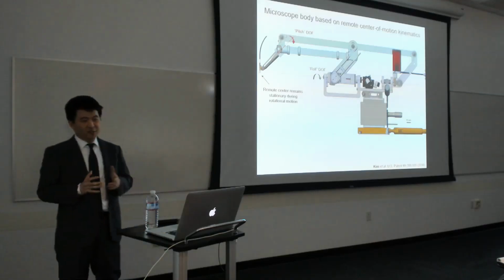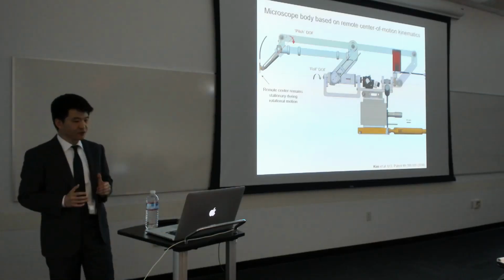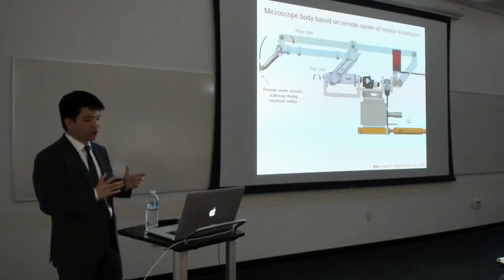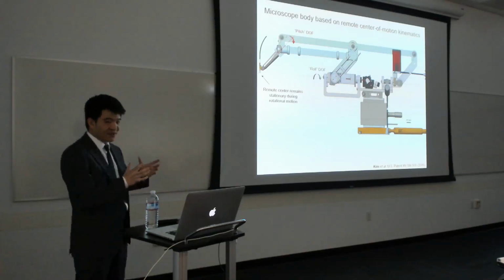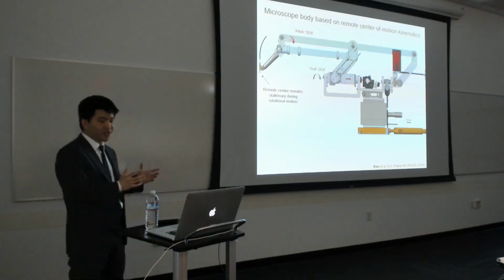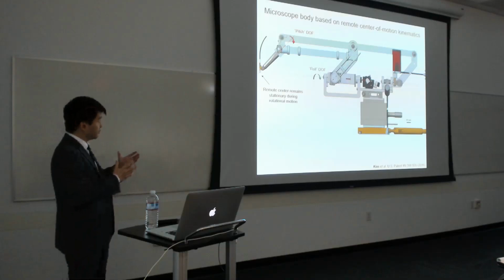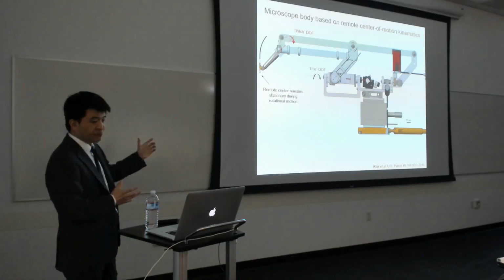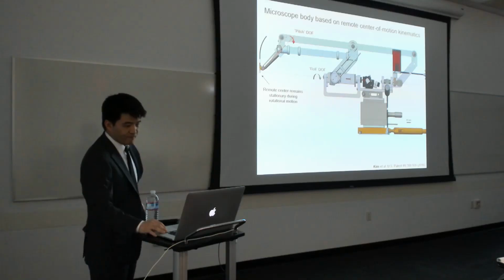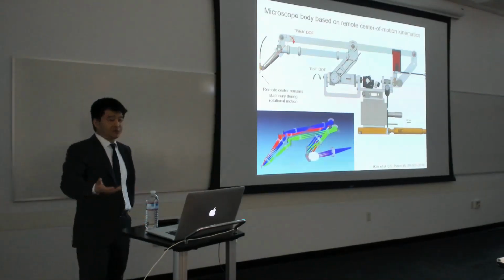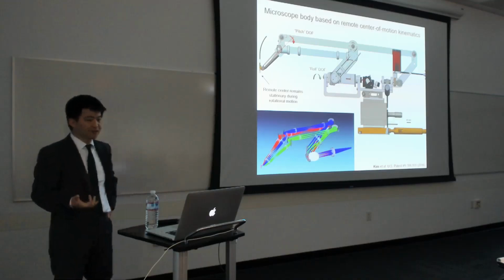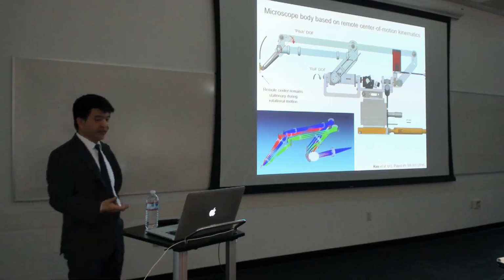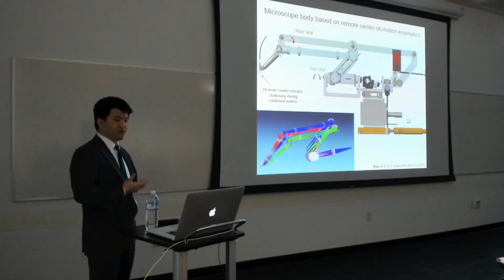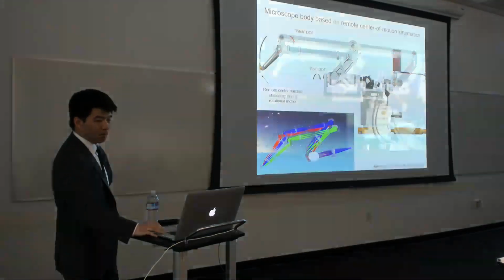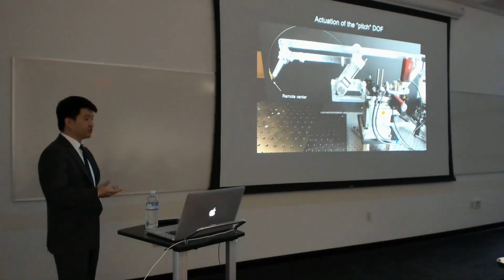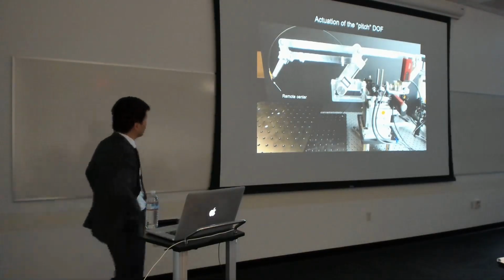So the octopus microscope is based on a remote center of motion kinematics originating from the field of surgical robotics. The idea of remote center of motion is to constrain the movements of a robot such that at a particular point, the remote center remains stationary during rotational motion. In the octopus microscope, I place that remote center at the tip of the microscope front end. Excitation light is then delivered free space through the robot, and optical alignment is maintained during rotational actuation. In fact, the full microscope, including the rotational degrees of freedom, was simulated in one ZEMAX model. Here's an example video illustrating the pitch degrees of freedom of the octopus microscope implemented remote center of motion.